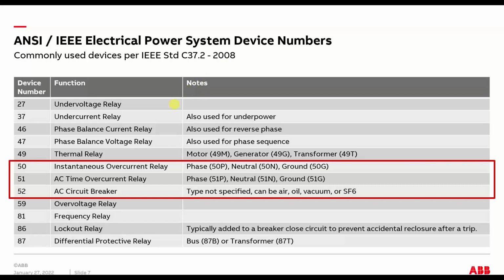And the device numbers basically go from 1 to 99. So this is just a very, very shortened list of the high points of what you've got to know if you're a casual user of relays. And really the big ones are device 52, which is the actual circuit breaker, device 51, which is your time delayed overcurrent, and then device 50, which is your instantaneous overcurrent. And then I'll get to the next slide.